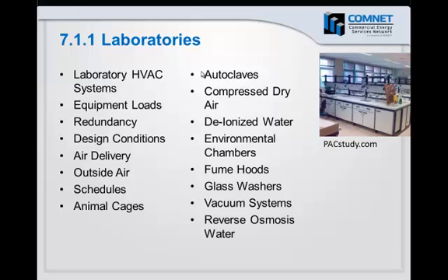I'm not going to go through each of these topics. I'm just going to touch on a few of them. Design conditions for laboratories tend to be a lot tighter. Heating is often 70 and cooling 72. There's also more stringent or more rigorous humidity requirements in many laboratory spaces, but these would be modeled the same between the baseline and the rated building.